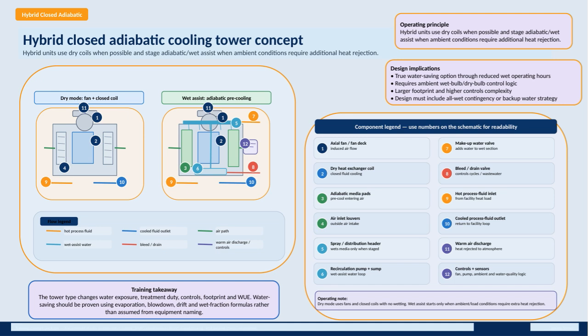Designing these systems brings some important implications. They require sophisticated control logic that monitors ambient wet bulb and dry bulb temperatures to decide when to switch between dry and wet modes. Because of the added components like spray headers, recirculation pumps, and makeup water valves, the footprint is larger and controls are more complex. Also, an all-wet contingency or backup water strategy must be included for periods requiring continuous wet operation.